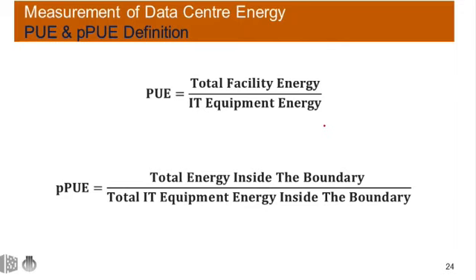The common term used and metric used for data center energy efficiency is PUE, power usage effectiveness. It's considered to be the industry preferred metric for measuring infrastructure energy efficiency for data centers. There is also a metric termed partial power usage effectiveness, which was originally created to avoid what was a misuse to some extent of PUE when only part of the total power was being considered. And I can explain a little more about that in some of the examples I'm going to present shortly.